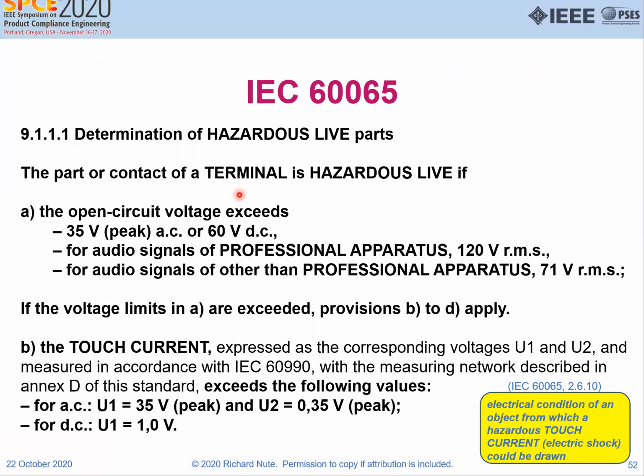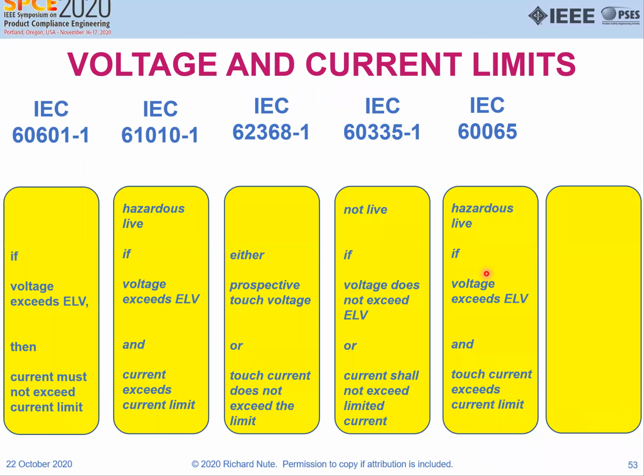A part or contact of a terminal is hazardous live if the open circuit voltage exceeds this, and if the voltage limits are exceeded, parts B to D apply. And it talks about touch current. Touch current exceeds the following values. Their voltages are measured at 990. So hazardous live if the voltage exceeds the limit and touch current exceeds the current limit.